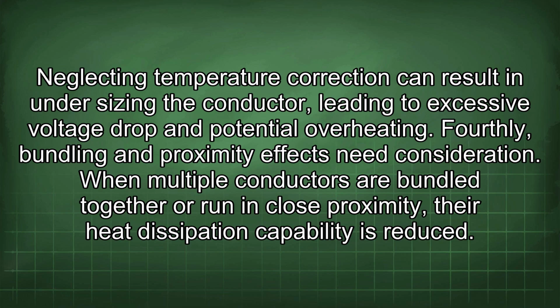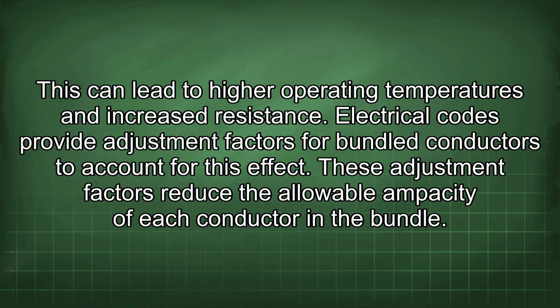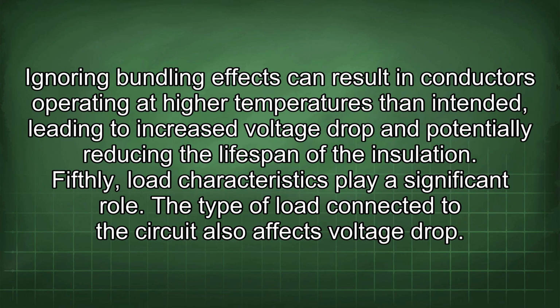Fourthly, bundling and proximity effects need consideration. When multiple conductors are bundled together or run in close proximity, the heat dissipation capability is reduced. This can lead to higher operating temperatures and increased resistance. Electrical codes provide adjustment factors for bundled conductors to account for this effect. These adjustment factors reduce the allowable ampacity of each conductor in the bundle. Ignoring bundling effects can result in conductors operating at higher temperatures than intended, leading to increased voltage drop and potentially reducing the lifespan of the insulation.